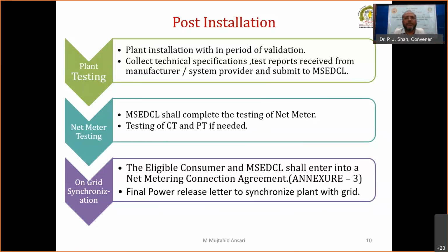If CTPT replacement is needed, as already discussed, in case of old cubical meters the capacity and accuracy are somewhat smaller. So we have to increase the accuracy of the CTPT to 0.5S and 0.2S as per MSEDCL norms. Also, earlier CTs had a burden up to 50 VA, but now new CTs have norms of 20 VA burden necessary for connecting the net metering system.